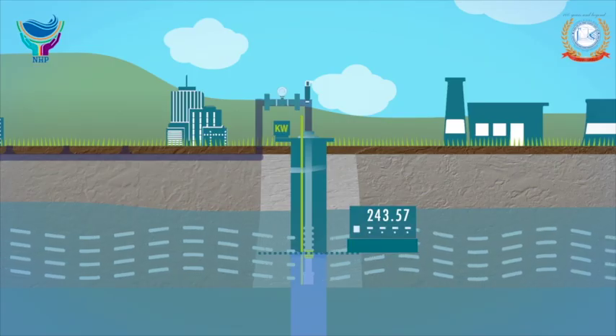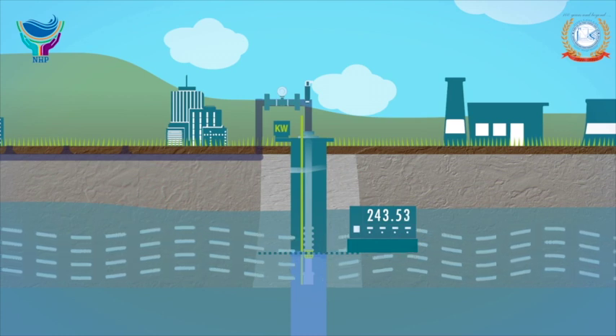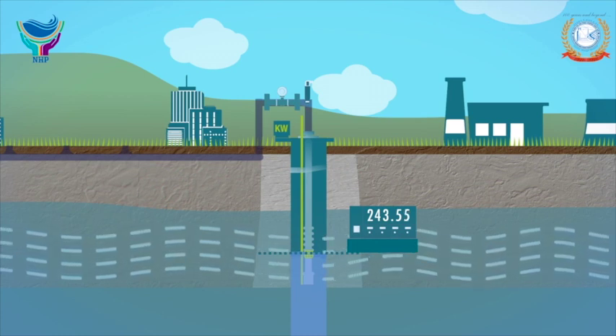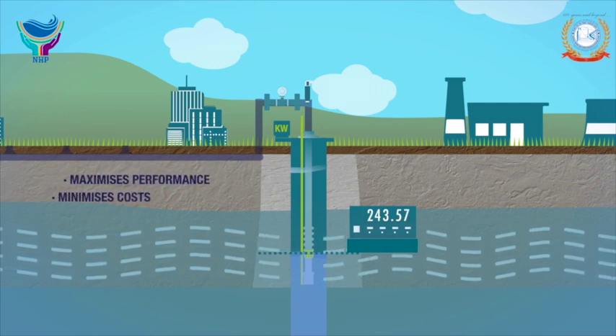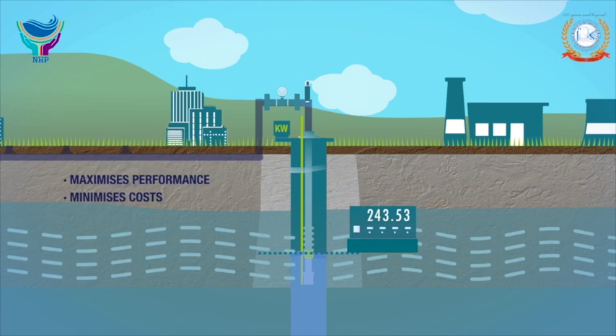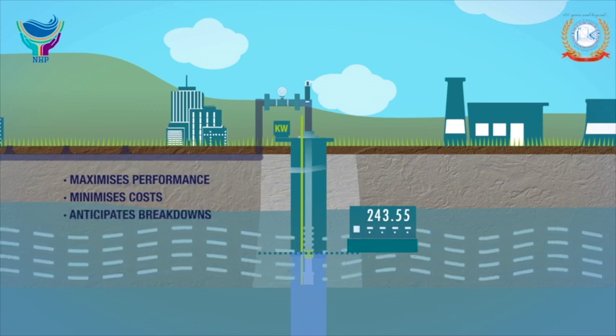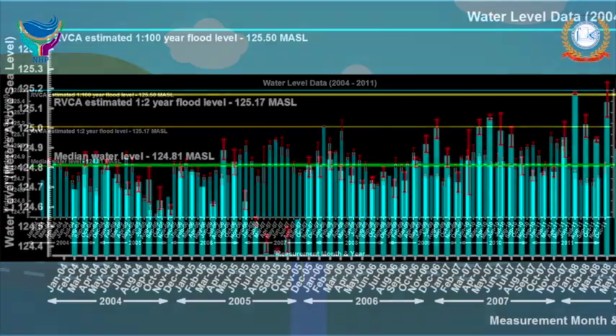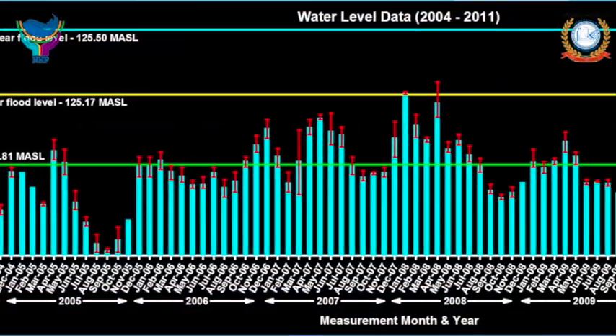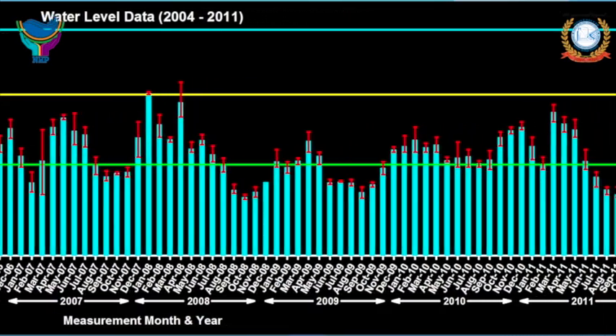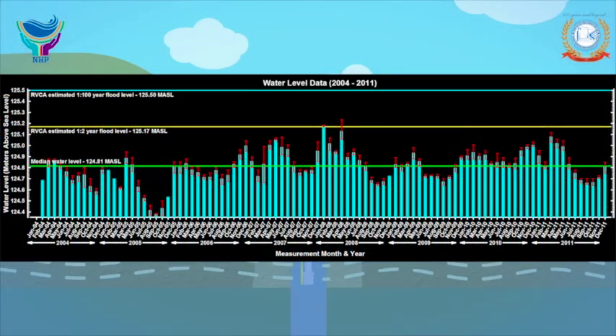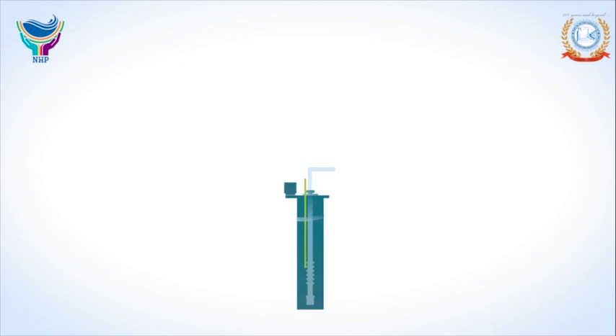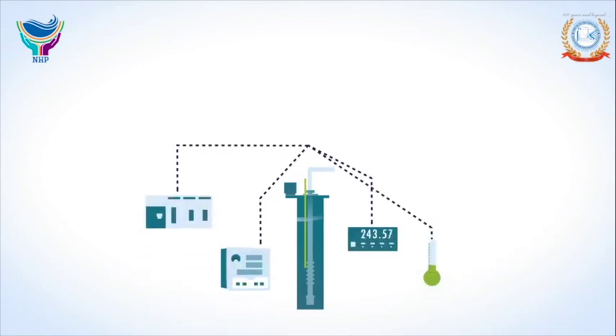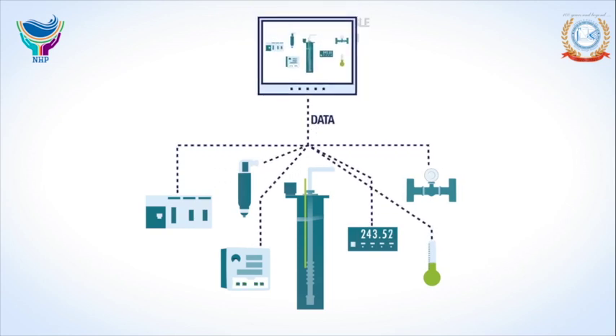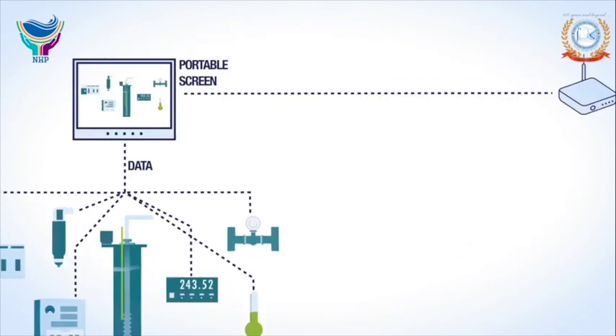The need of a testing facility for the system. The automatic water level monitoring systems need to be programmed to make measurements in bore wells at a specified frequency over long periods of time, as these measurements are the principal source of information. Long-term systematic measurements provide essential data which is needed to evaluate changes in the resource over time and develop models for management, and to achieve it, it requires suitable sensors as well as an automated monitoring system.